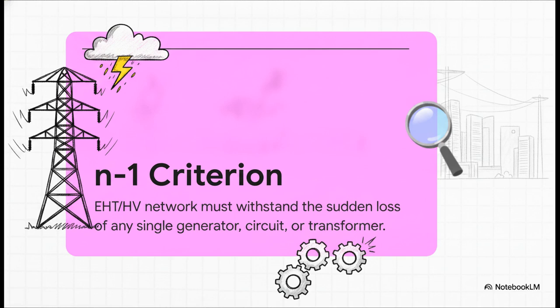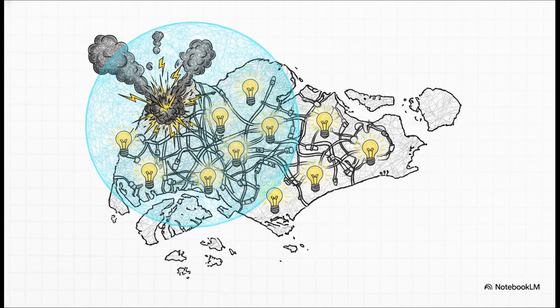Enter the single contingency, or the N-1 criterion. This isn't just a suggestion, it's a completely non-negotiable planning standard dictated by the transmission code. It requires Singapore's high-voltage grid to instantly absorb the sudden, unexpected loss of any single major piece of equipment. If a massive generator trips offline at 3 a.m. or a 400 kilovolt transmission line just severs, the system must withstand it. Every single time. And withstand it has a very specific, legally binding meaning here.